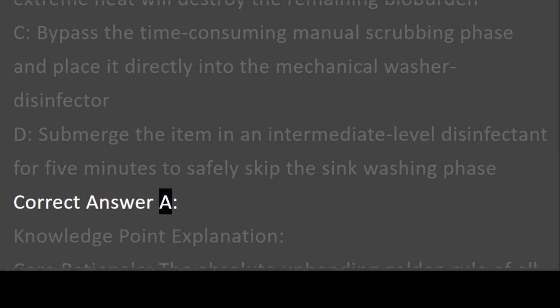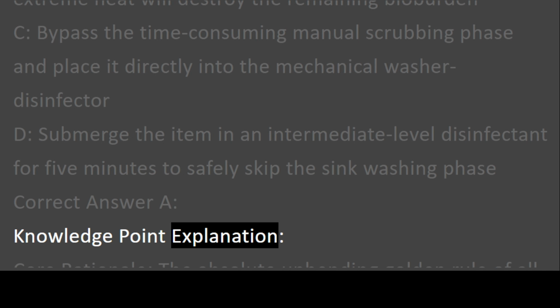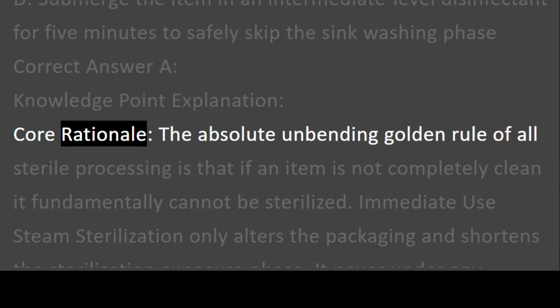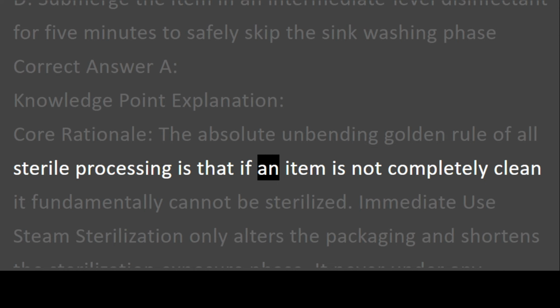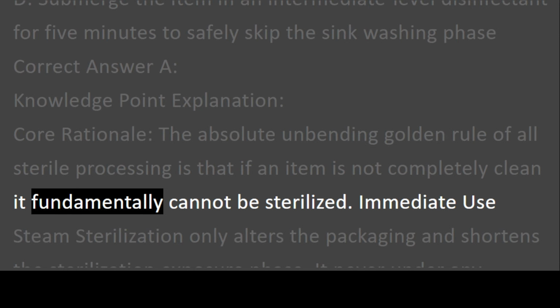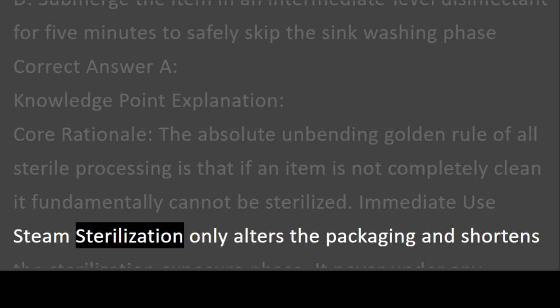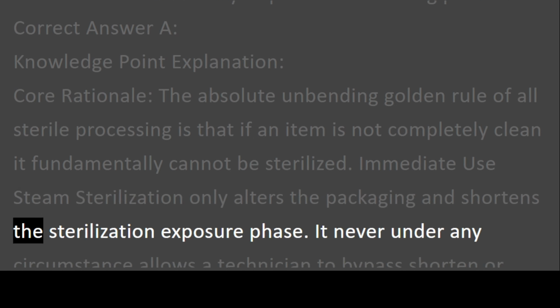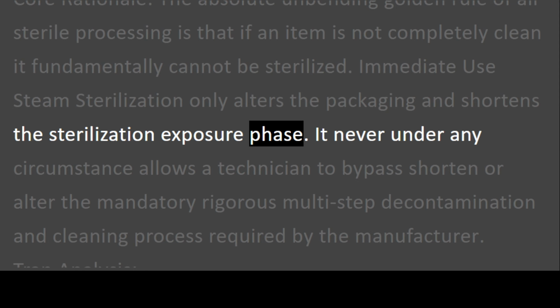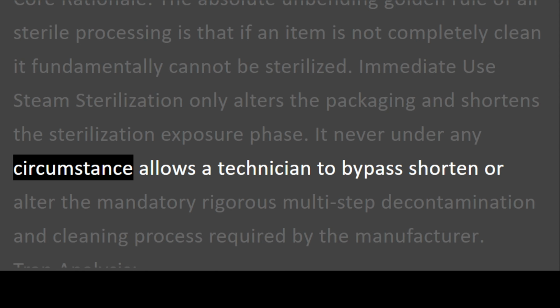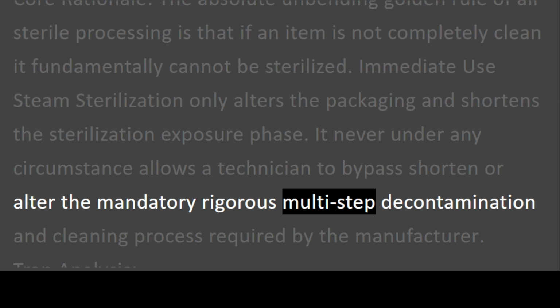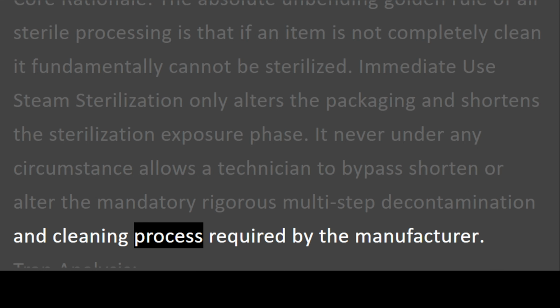Correct answer A. Knowledge point explanation. Core rationale. The absolute unbending golden rule of all sterile processing is that if an item is not completely clean, it fundamentally cannot be sterilized. Immediate use steam sterilization only alters the packaging and shortens the sterilization exposure phase. It never under any circumstance allows a technician to bypass, shorten, or alter the mandatory rigorous multi-step decontamination and cleaning process required by the manufacturer.